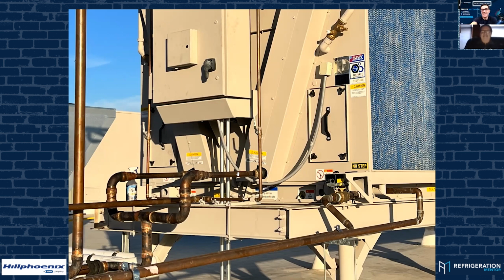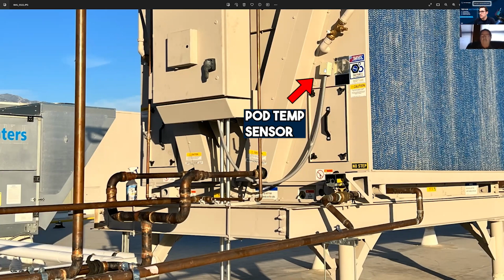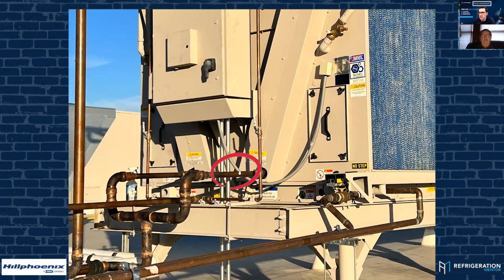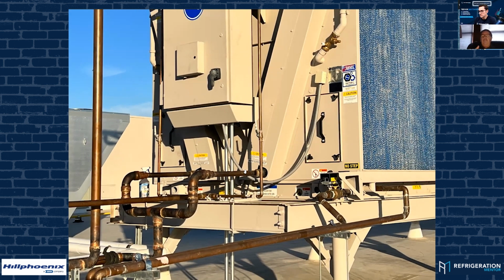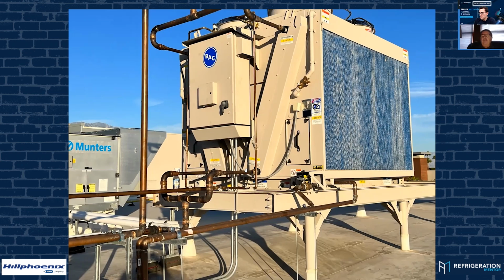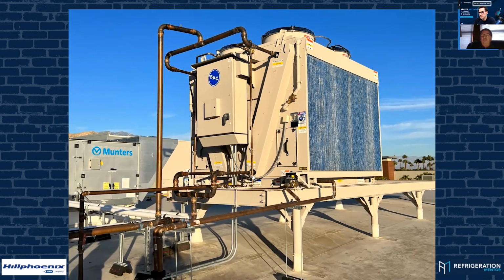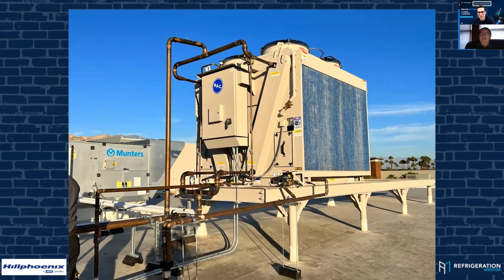Yeah. So, just to be clear, so everyone knows, right here would be your pad sensor, in behind the pad. That's correct. And then right down here, around here, 4 inches out of this line, you would insulate the outlet drop leg sensor, mounted at 5 and 7 o'clock. Yep. The reason we don't mount it on the bottom is there might be oil in the pipe, and that's going to insulate the sensor. What a coincidence. That's the same as we do in regular HFC systems on DX coil bulbs. No, you're kidding. Imagine.